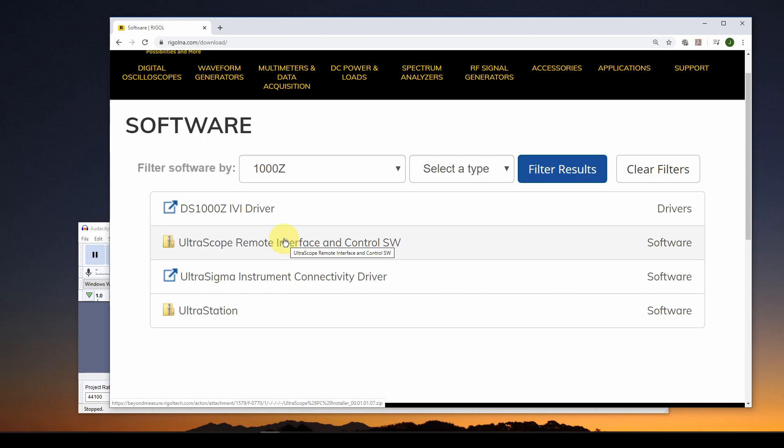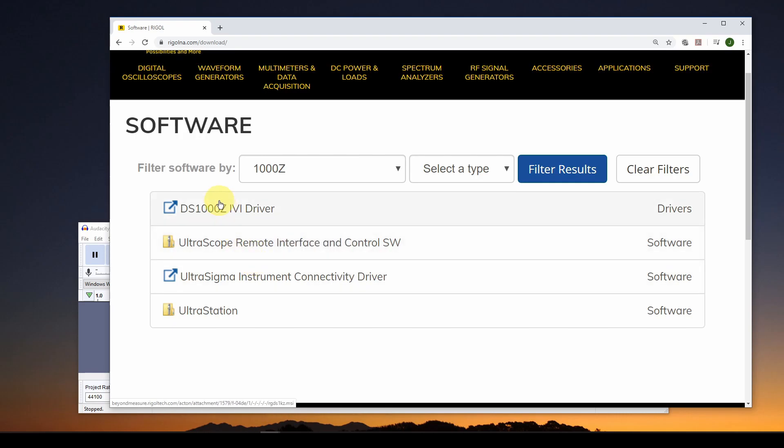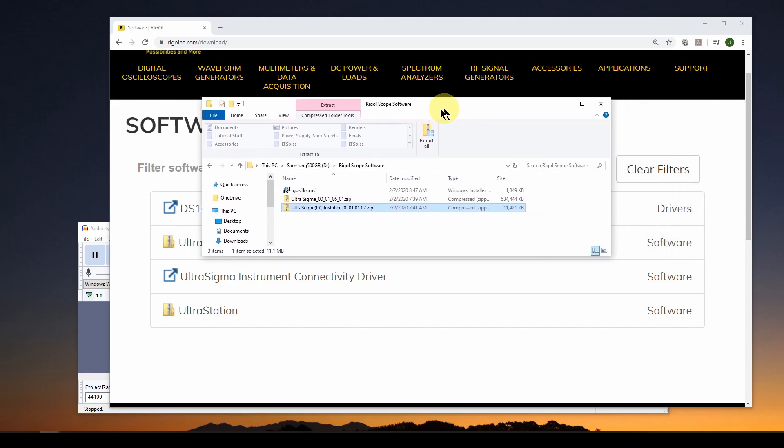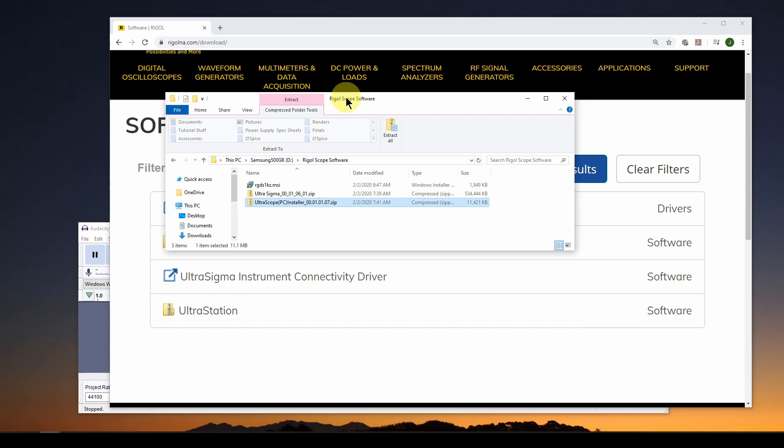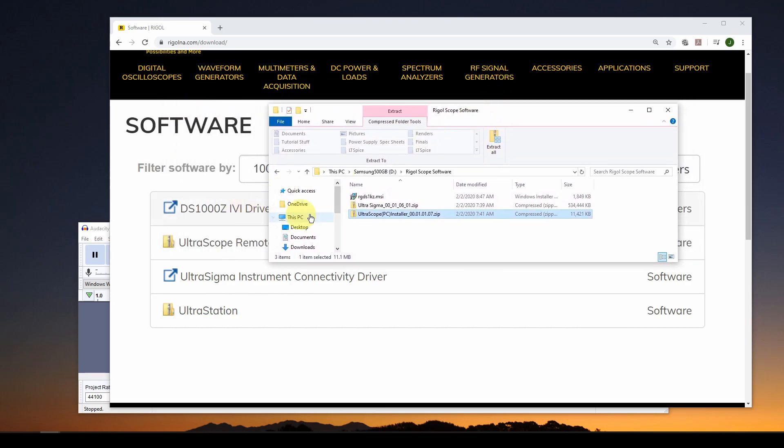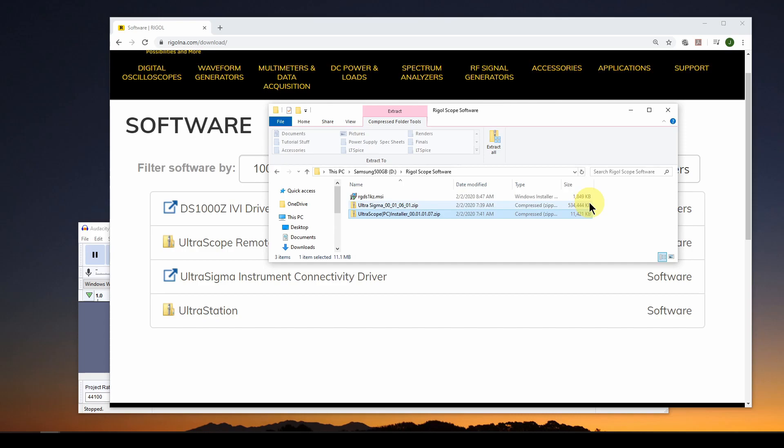And then if you want to have a window on your Windows machine that shows you a duplicate of the oscilloscope display and allows you to communicate with the oscilloscope and to change settings remotely on your PC, you're going to want that. So download these first three, and it's going to take a while. But when you get them all done, you're going to have the RGDS MSI, which is this IVI driver, and then you're going to have UltraSigma at 534 megabytes, and then UltraScope, which is much smaller, and that is the oscilloscope on your desktop.